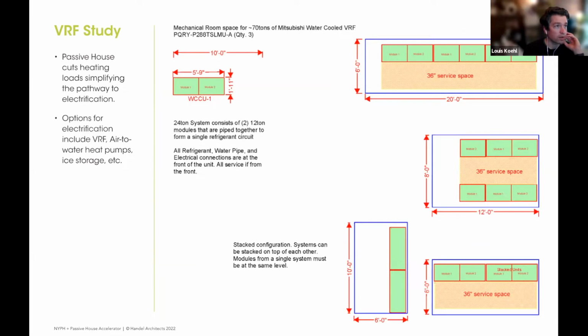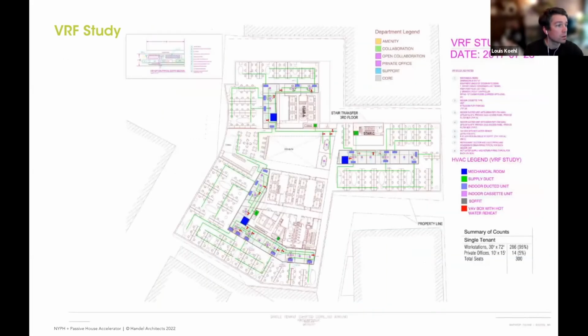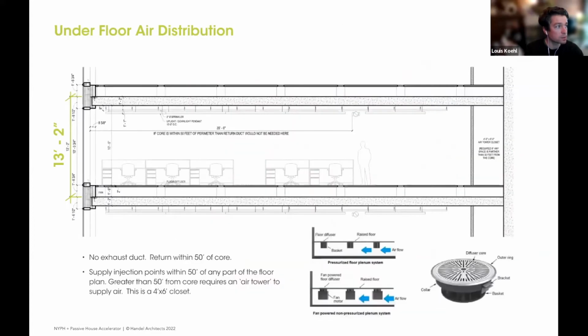We did look at a water source VRF option, looking at how much space on each floor would be required for the VRF condensers, and did a layout showing these VRF rooms. Obviously that requires a lot of space on the floor, so you lose a lot of leasable space, and there's also a lot of refrigerant running around. There were several reasons why this was ultimately not selected.